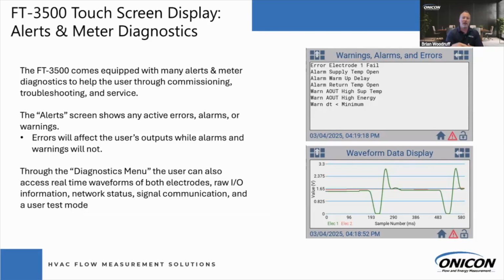So thankfully, you're able to go to these warnings or alarms to tell you, and sometimes if it's just a warning, it's just able to still read flow, but there's something you need to look at in your system. Alarms or errors, then you really need to dive into. It could be as simple as a temperature sensor not touching the application and getting an accurate reading to maintain, say, a chill water at 10-degree delta T and so forth.